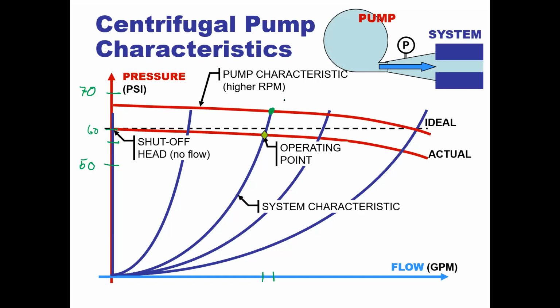If we have a higher RPM, we can change our pump characteristic to increase our pressure. And same thing if we decrease it: if we decrease our RPM, we'll decrease our pressure. So gallons per minute is based on the system: how open the valve is, how much restriction to flow we have. It all means the same thing. The system characteristic is for the flow, and the pump characteristic is all based on the pressure, the RPM that we're running at.